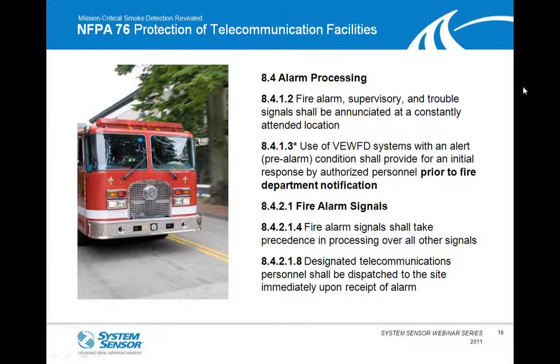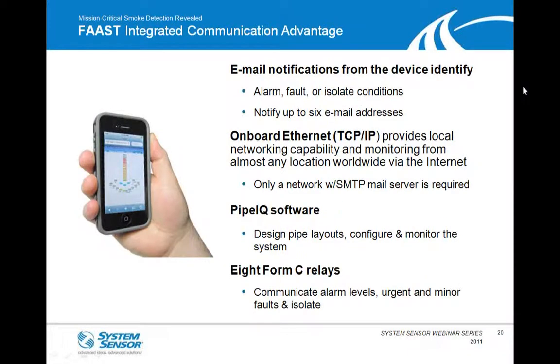So how can we notify people as efficiently as possible? Well, with FAAST, we do have several things that provide a more integrated communication advantage. The first of which is email notifications from the device, which are sent to identify alarm, fault, and isolate conditions. And when we say alarm, that does include the alert or pre-alarm level. An onboard Ethernet or TCP/IP basically provides that local networking capability and monitoring from just about anywhere around the world. In addition, if you set up the network with a SMTP mail server, that does enable the email notifications.